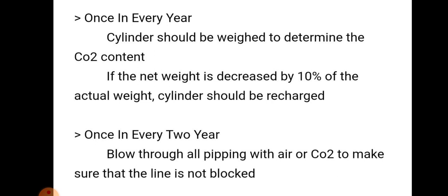Once in every 2 years, we have to blow through all piping with air or CO2 to make sure that line is not blocked.